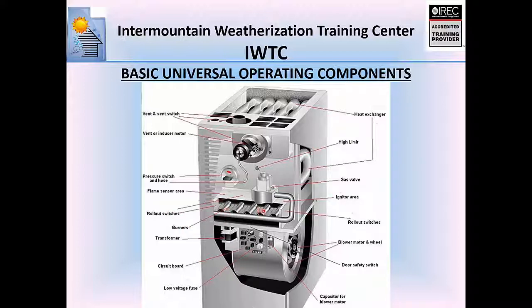These are in-shot burners. If I didn't know what BTU input this furnace was, how could I figure it out? Count the burners and times by 20,000. 20, 40, 60, 80, 100,000 BTUs.